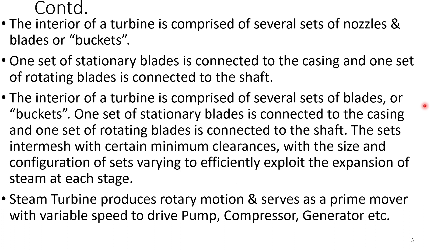The interior of a steam turbine has several sets of nozzles, also called buckets or blades. One set of stationary blades is connected to the casing, and one set of rotating blades is connected to the shaft. The sets mesh with certain minimum clearance, with the size and configuration of sets varying to efficiently exploit the steam expansion at each stage.